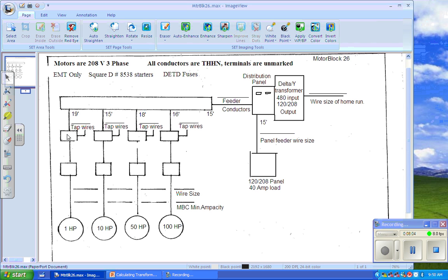Up to 45 amps. So I could have, remember, this is not a circuit that's going to, if it's going to go short, it's going to go phase to phase type thing, and it's going to turn itself off very quickly. So 45 amps is not a big deal. And generally we don't need to do that. We'll have a 15 amp circuit breaker or a 15 amp fuse that will be supplying the control circuit that we can set up inside one of the motor starters.